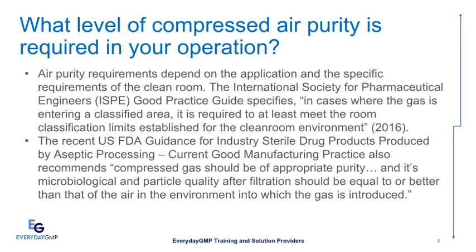What level of compressed air purity is required in your operation? Air purity requirements depend on the application and the specific requirements of the clean room. The International Society for Pharmaceutical Engineers (ISPE) Good Practice Guide specifies that in cases where the gas is entering a classified area, it is required to at least meet the room classification limits established for the clean room environment. The 2016 USFDA guidance for industry on sterile drug products produced by aseptic processing also recommends that compressed gas should be of appropriate purity, and its microbiological and particle quality after filtration should be equal to or better than that of the air in the environment into which the gas is introduced.